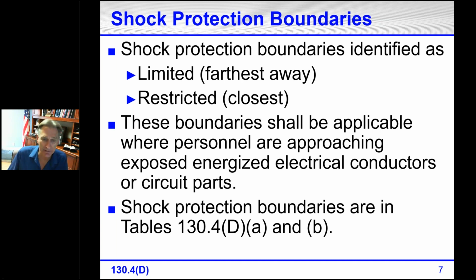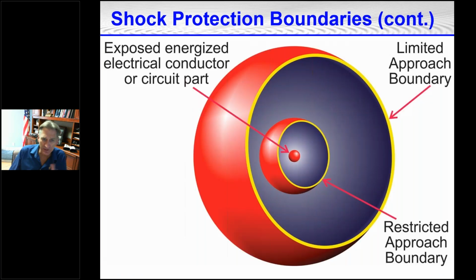Shock protection boundaries, where are they located? In table 130.4 D, A, and B. All right, so here's another drawing with just the two shock boundaries. In the center, that little red ball represents live electrical conductors or circuit parts. The furthest boundary from that is called the limited approach boundary. The next boundary in, the closest of the boundaries, is called the restricted approach boundary.